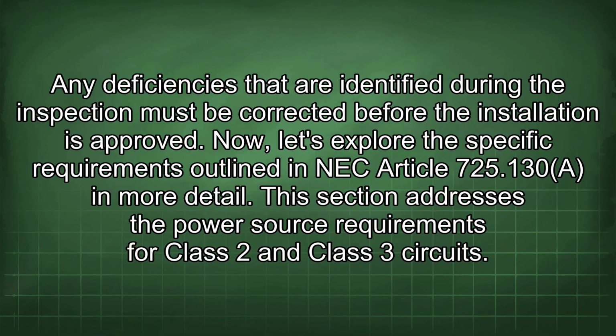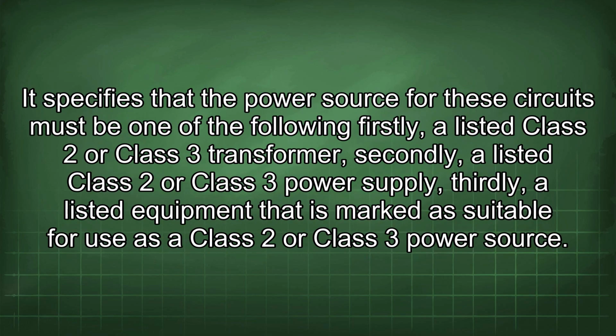Now, let's explore the specific requirements outlined in NEC Article 725.130 in more detail. This section addresses the power source requirements for Class 2 and Class 3 circuits. It specifies that the power source for these circuits must be one of the following: firstly, a listed Class 2 or Class 3 transformer; secondly, a listed Class 2 or Class 3 power supply; thirdly, listed equipment that is marked as suitable for use as a Class 2 or Class 3 power source.